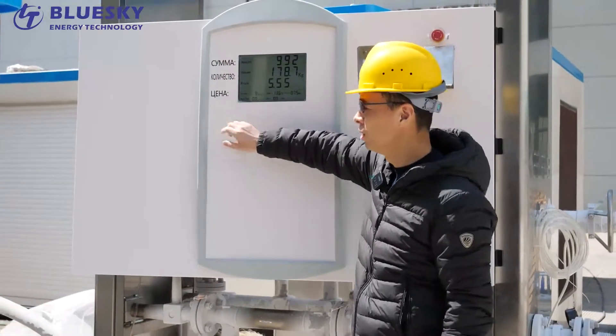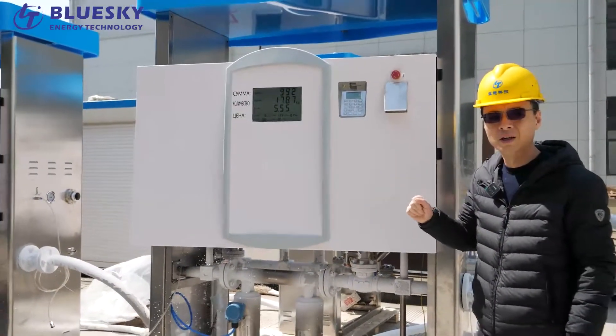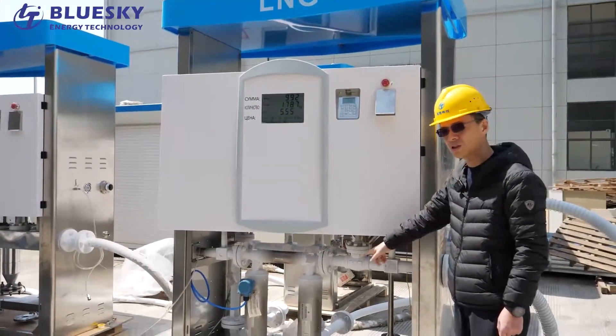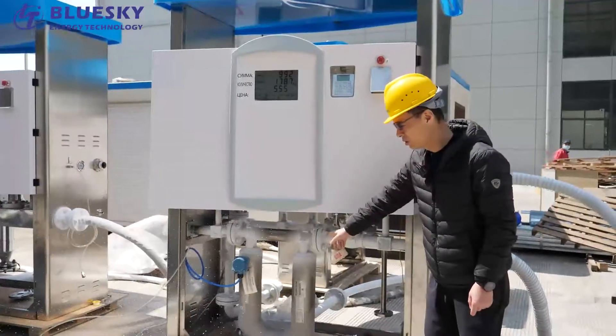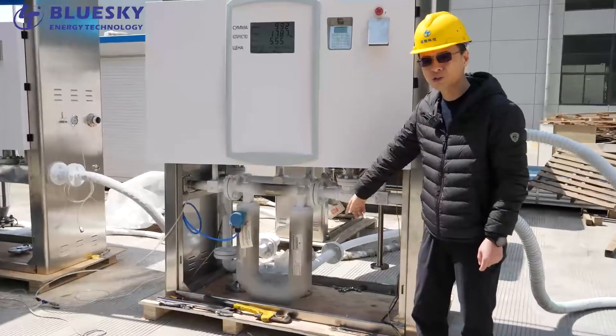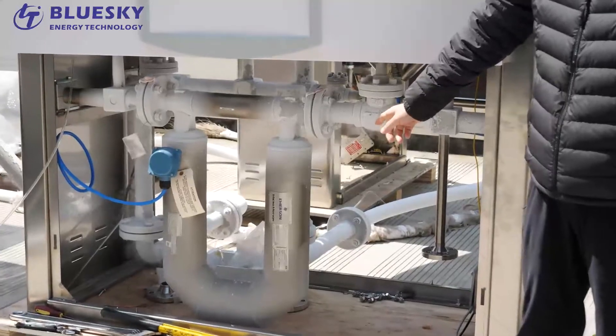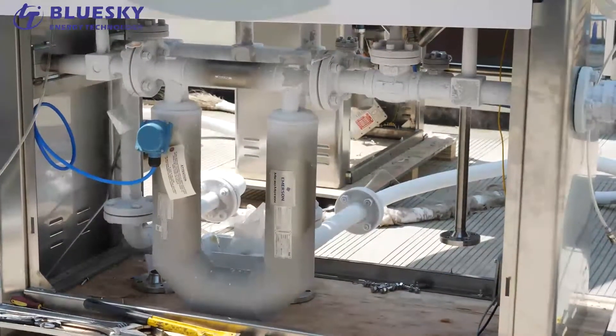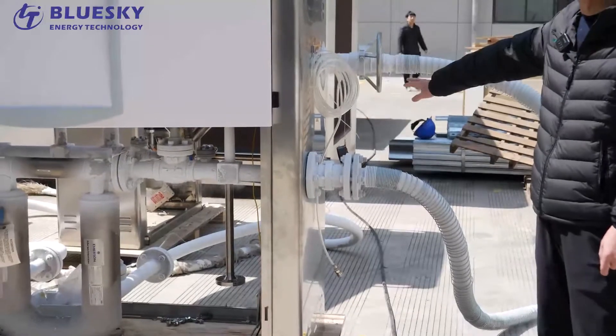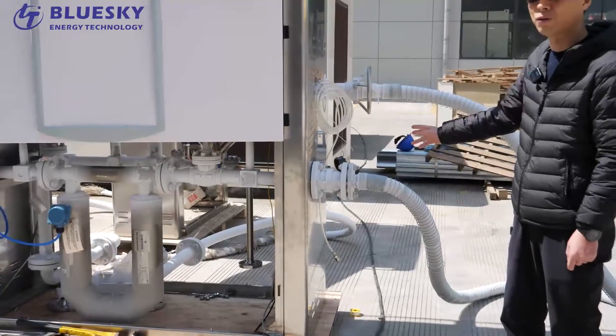These two machines are a little different from a normal standard LNG dispenser. On the underside of the dispenser you can see the mass flow meter is a two-inch Micro Motion unit. The maximum flow rate can reach 800 liters per minute. All the pipelines are two-inch as well, and the connector is a GC cutter type — this is a high-flow-rate standard.